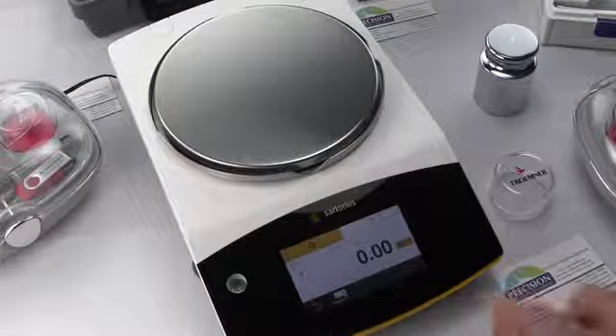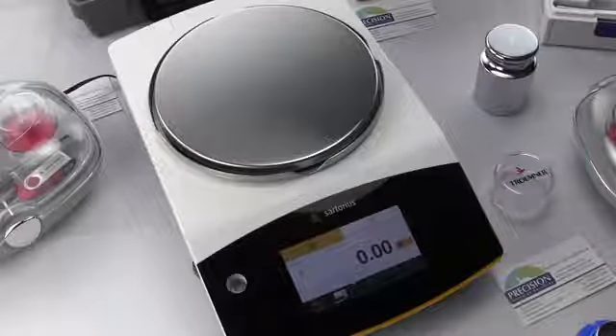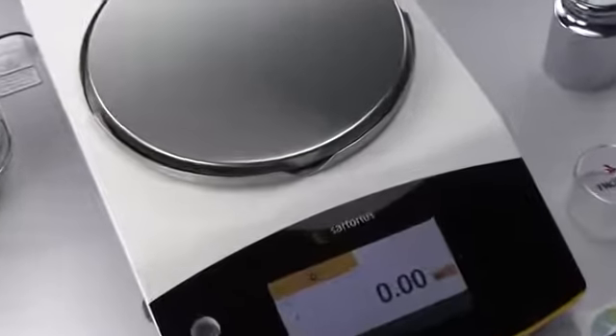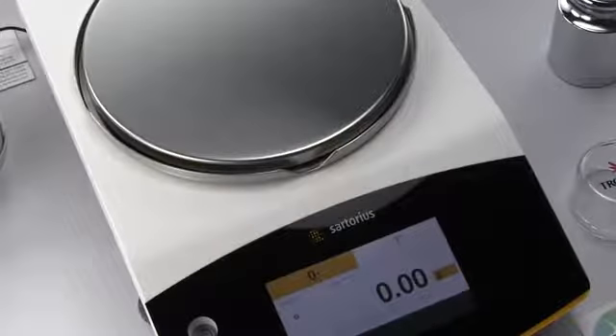This balance also has isocal. So isocal, if you notice in the screen here, it says isocal. And what isocal basically does is it would perform an internal calibration when the balance is turned on. And there's set periods of time dependent upon the model. It goes by the time of last calibration. Some models it's 4 hours, some models it's 6 hours, and it also goes by the change in temperature in the area. So performing external or manual calibration, again, you have to purchase the optional calibration weights.